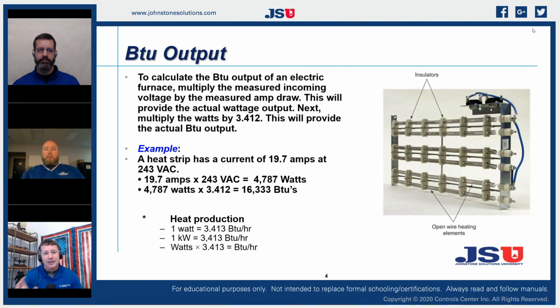So if we look at an electric heat strip, we can simply take our meter, measure the amps that are being drawn by that heater, and then take our leads, put our meter on voltage, AC, and we can check the voltage that is being applied to that heater. Now we can get the exact watts. So like last week when we were talking about using Ohm's law and taking a piece of our pie chart to take two, if we have two known factors, we're going to have our third, we're going to find it, right? It's just a mathematical calculation. Well, when we're talking about watts, we are simply multiplying our measured amp draw for that element times the voltage that's being applied across it, and that gives us our watts. That's how much heat energy is being produced from our electric energy.